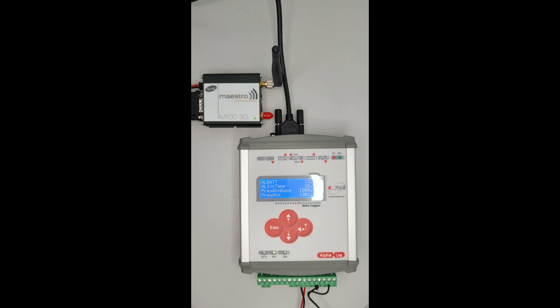Second, we need to check the COM1 serial port activity, to check if communication between AlphaLog and the radio modem is established. From the measurement list, press escape 2 times to reach the main menu, go to Diagnostic and press Enter, go to Serial lines, press Enter and scroll the up and down arrows to reach serial port 1. The numbers corresponding to the receiving and transmitting activity should change frequently.